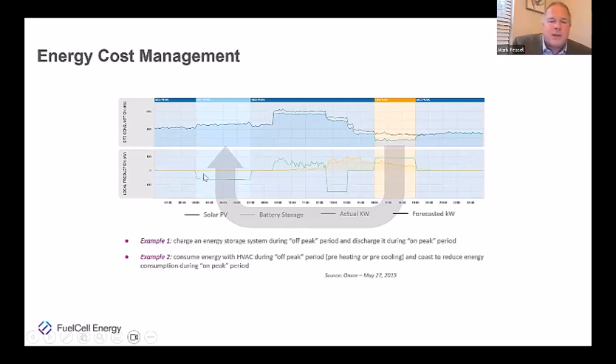So that's exactly what happens here. You can notice that in the middle of the night, the green line going negative means the battery is being charged. Now, you'll notice right around 8 a.m. the battery is discharging. Why would that be, since it's not on-peak time, just mid-peak? Remember that demand peak we talked about, 800 kW? The system forecasted that site was going to use more than that demand peak, so it dispatched the battery to shave that peak and avoid the fine.